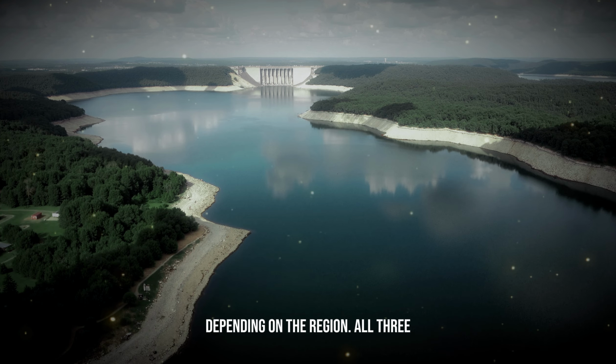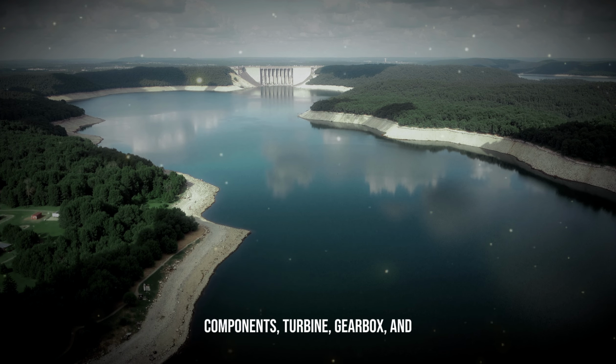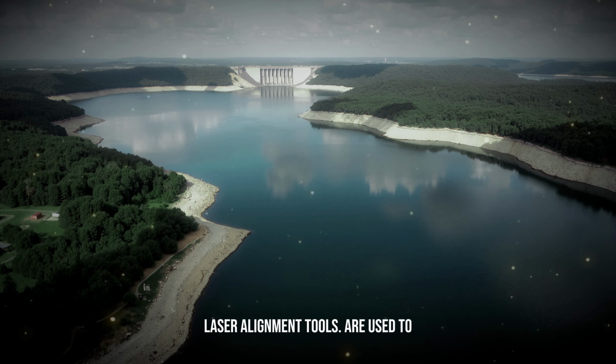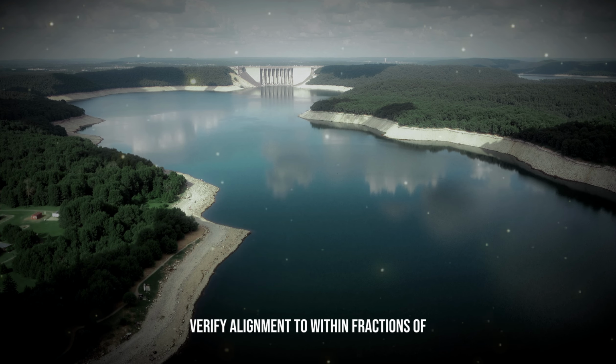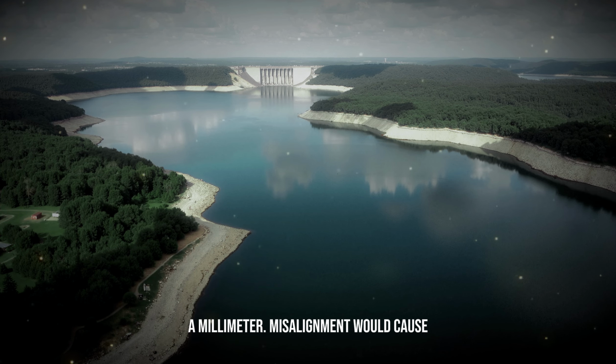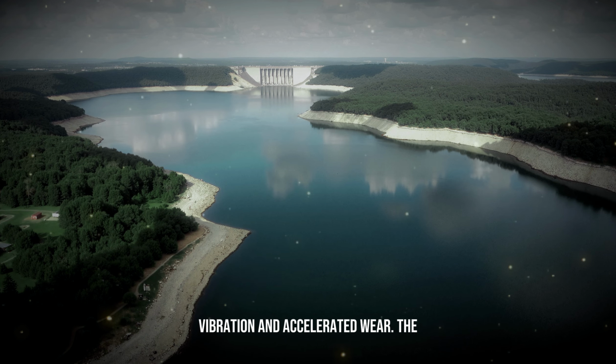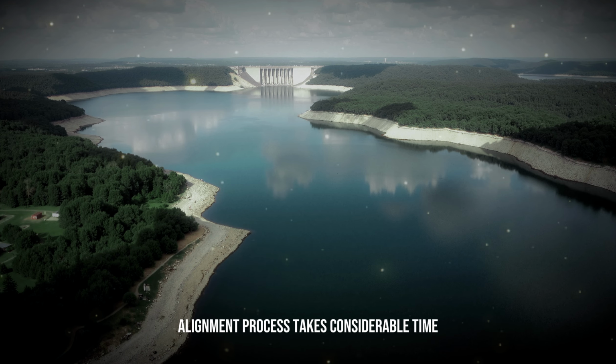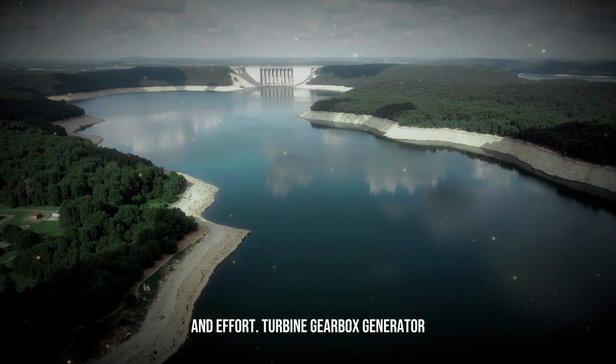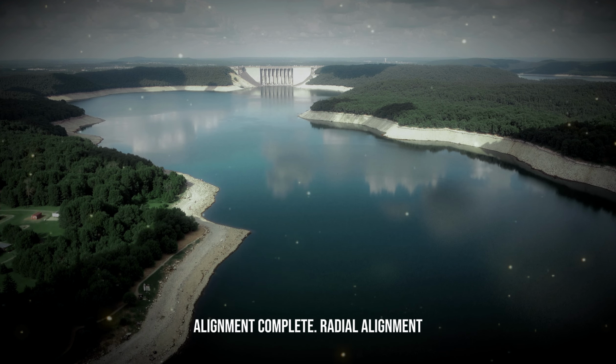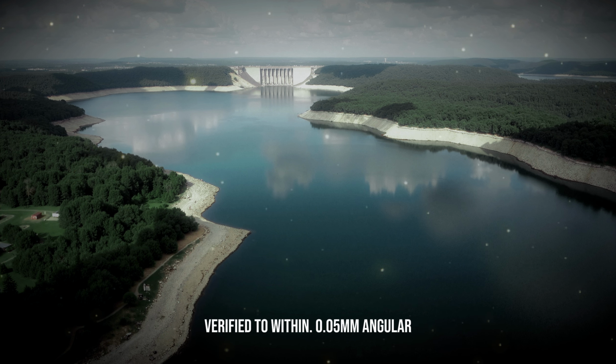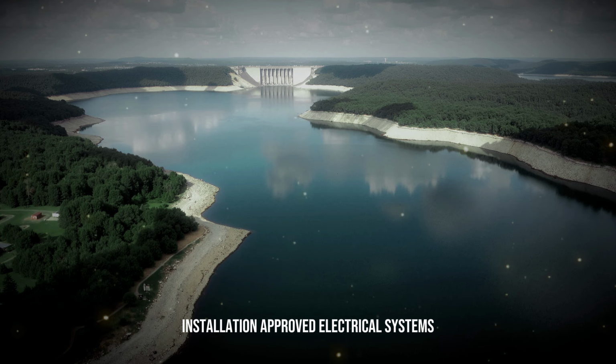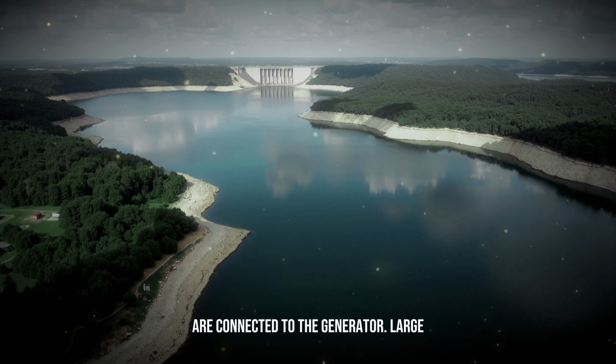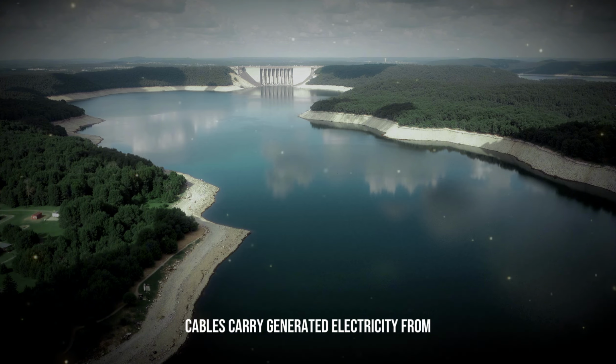All three components, turbine, gearbox, and generator, must be perfectly aligned. Laser alignment tools are used to verify alignment to within fractions of a millimeter. Misalignment would cause vibration and accelerated wear. The alignment process takes considerable time and effort. Turbine gearbox generator alignment complete. Radial alignment verified to within 0.05 millimeters. Angular alignment verified to within 0.01 degrees. Installation approved. Electrical systems are connected to the generator.